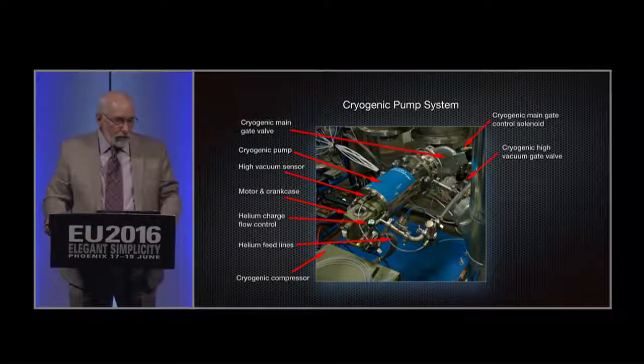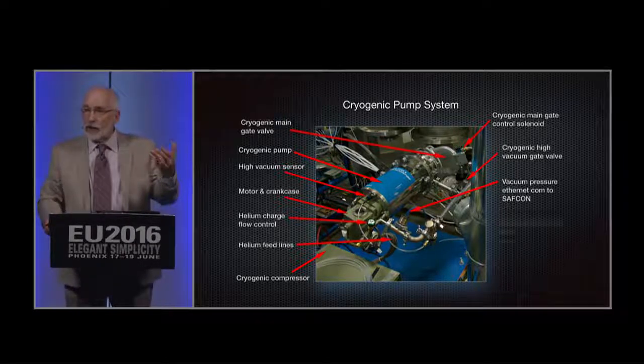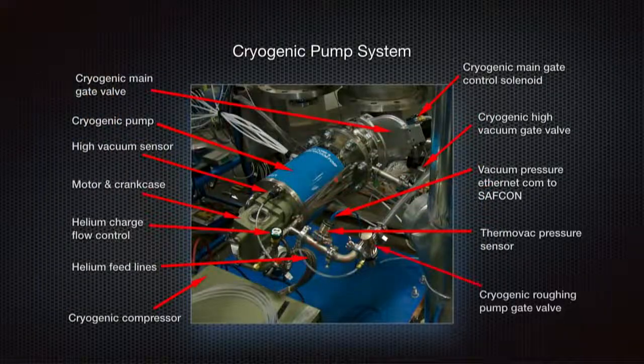And there's really not many things in the way of moving parts. It basically uses helium to bring the temperature of the cryo pump down to a place where it condenses the gas.